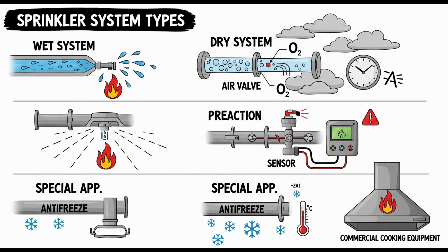A supervised indicating control valve is permitted to be installed in the riser assembly above the main pre-action or deluge valve. Above the main valve. Yes. This valve, which should be supervised open during normal operation, allows maintenance personnel to perform full-function trip testing of the system, testing the detection, the valve trip mechanism, etc., as required by NFPA 25, the testing and maintenance standard, without actually discharging a huge volume of water into the entire system piping network.